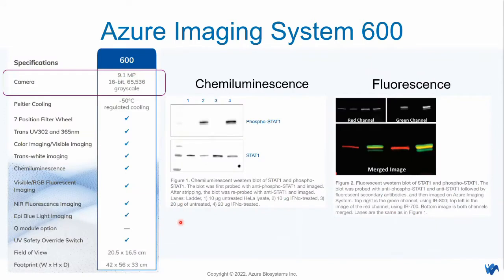Regarding the technology evolution, if you look at the specs of the Azure Imaging System 600, the camera specification contains a 9.1 megapixel camera with 16-bit resolution, giving you 65,000 grayscale steps. This camera can capture all images and signals from your gel — DNA gel, RNA gel, Western blot covering both chemiluminescence and fluorescence western, and even colorimetric western as well.